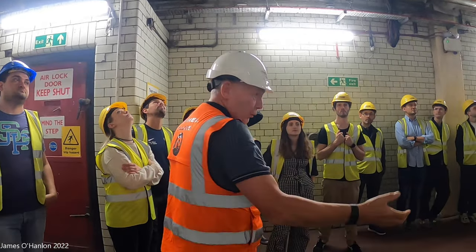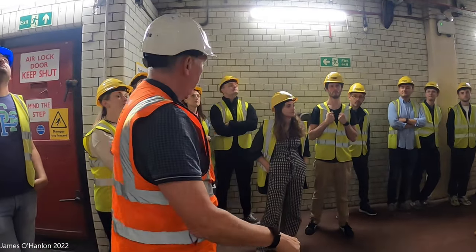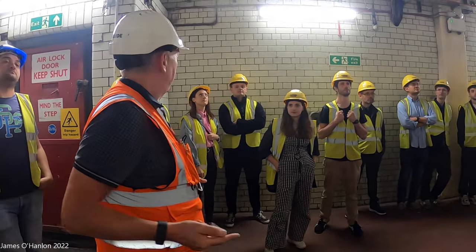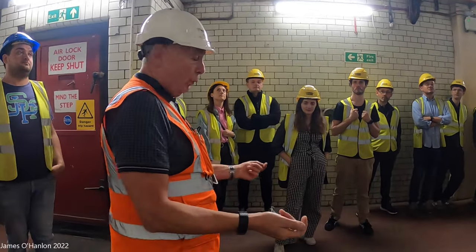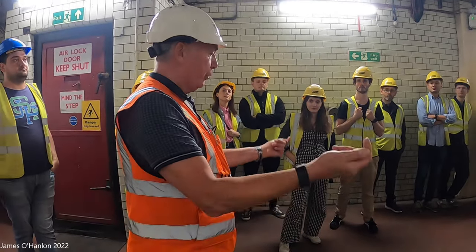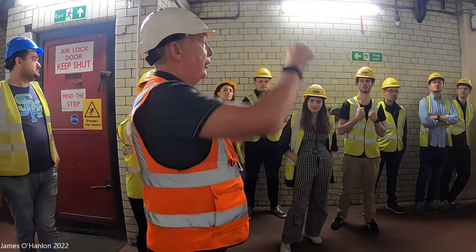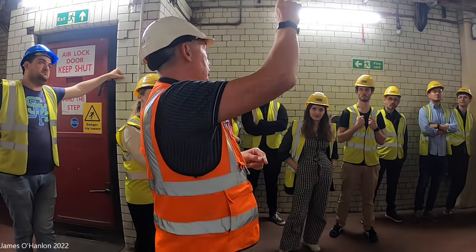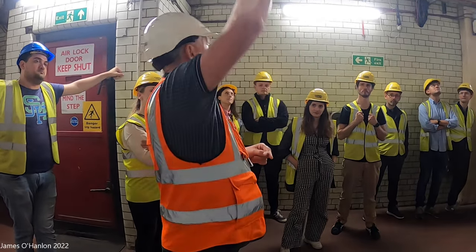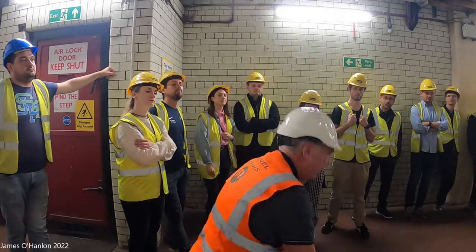It's going to come past us, go into the fan, and then send down a shaft about 120 feet deep, and it goes into the airways. Remember that diagram we showed you with the airways? It goes into those airways. Once it's in those airways, this little hole's drilled up onto the road, fresh air comes up, ventilates the tunnel, and then goes out through the flat section of the roof with its holes again, out through to the exhaust fan, straight up the chimney. That makes sense to everybody? It's positive pressure, fresh air in, foul air out.